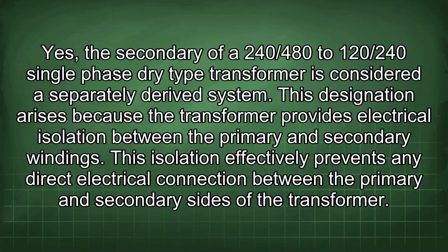Yes, the secondary of a 240/480 to 120/240 single-phase dry-type transformer is considered a separately derived system. This designation arises because the transformer provides electrical isolation between the primary and secondary windings. This isolation effectively prevents any direct electrical connection between the primary and secondary sides of the transformer.